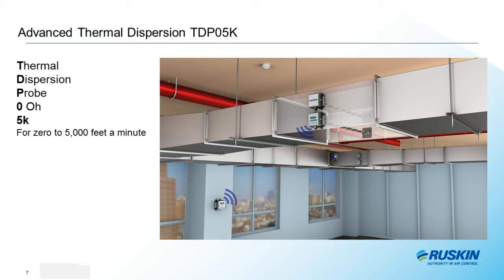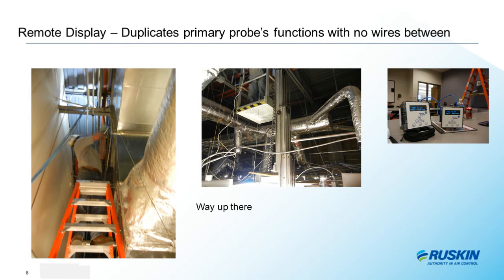The air measurement station is way up there, more than 16 feet above the floor, just below the roof deck. The man lift was used instead of a Spider-Man outfit to install the probes in a very bad location. We were only 3 feet away from the blower, just upstream from 2 horizontal branch takeoffs. We hooked up the wireless displays to a power supply on the desk, and we were able to configure the air measurement station, the BACnet interface, and read the airflow and temperatures from RTU1 and RTU2 from the comfort of our chair. Air measurement just got easier.